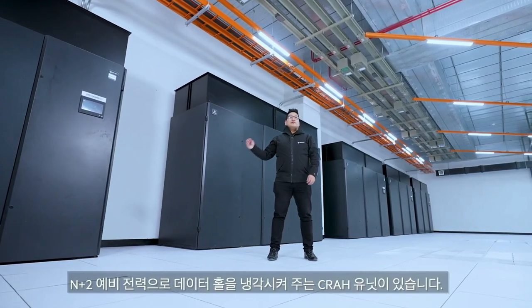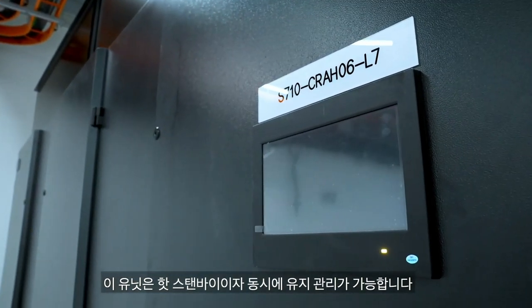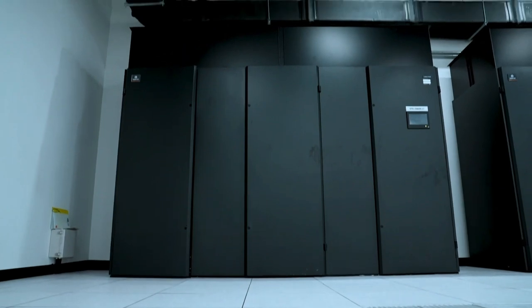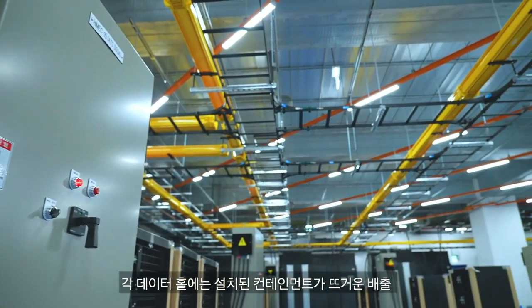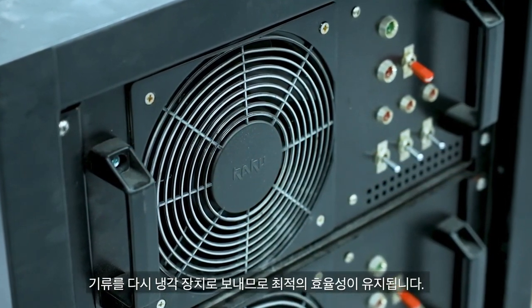These are the CRAH units which will provide cooling to the data hall with N plus 2 redundancy. It is a hot standby and concurrently maintainable. Containment can also be installed at each data hall to guide hot exhaust air flow back to the cooling unit, thereby maintaining optimum efficiency.